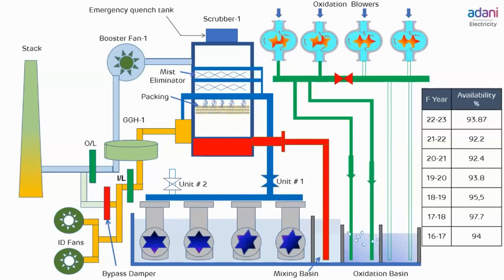The packing material is specifically designed packing with very high surface area so that gas to seawater contact is optimized at given packing volume. The capture of SO2 in the scrubber involves several physical and chemical processes, beginning with gas phase concentration and pressure driven mass transfer across the optimized liquid phase. Then chemical mechanisms take over to capture SO2. Hydrolysis, neutralization and oxidation reaction mechanisms help to stabilize the absorbed SO2 and prevent it from escaping the seawater liquid phase and returning back to the flue gas phase.